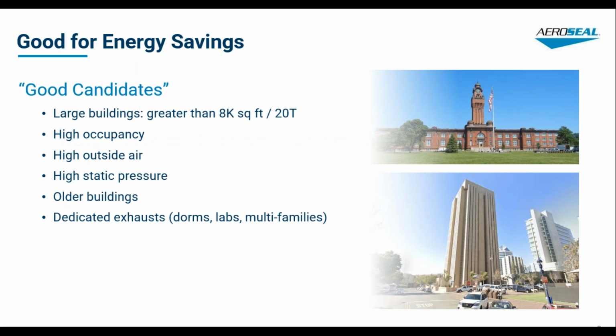75% of ducts leak 10 to 25%, so we care about them all the time. But there are some things we look out for if we're trying to make this a good energy project: larger buildings, anything with high occupancy, high outside air, the higher the static pressure the better for us, older buildings, and anything with dedicated exhaust. We also say anything above 10 horsepower or so is going to be a great candidate. Anything from 5 to 10, send it over and let us look at it, and we can figure out if that's going to make a great project or not.